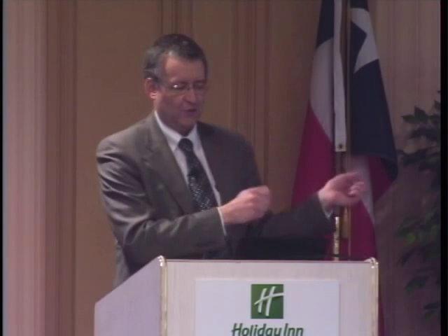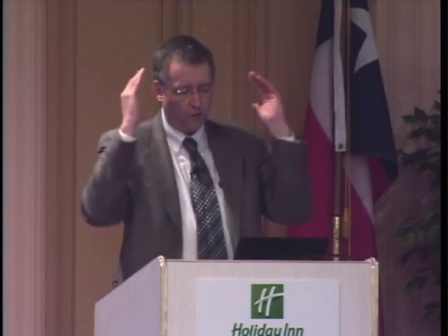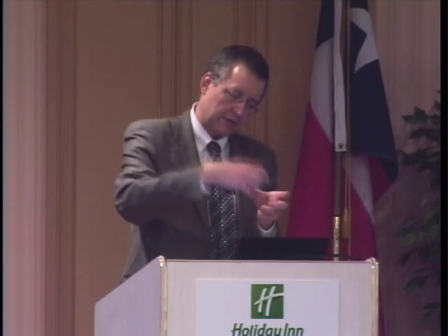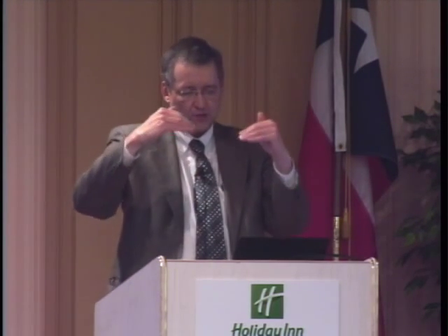So they go back, they get the new prescription made, and they come back 2 weeks later and they say, "Doc, these new glasses you prescribed, they're terrible. They're nothing like my old glasses. Those were great." So what are you going to do? You measure them in the Lensmeter. They're exactly the same power. And so perhaps there's a difference in base curve, the overall curvature of the lens. So you get out the lens clock and you compare the two, and you see if the base curve is different. And if so, then you have your diagnosis.